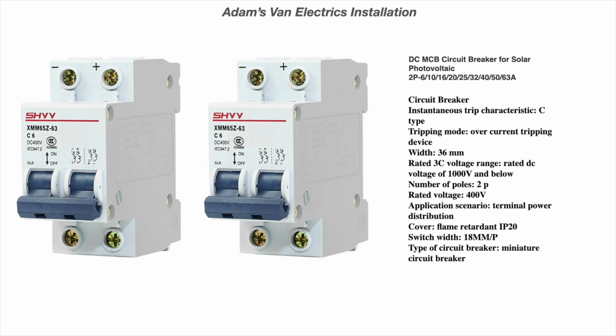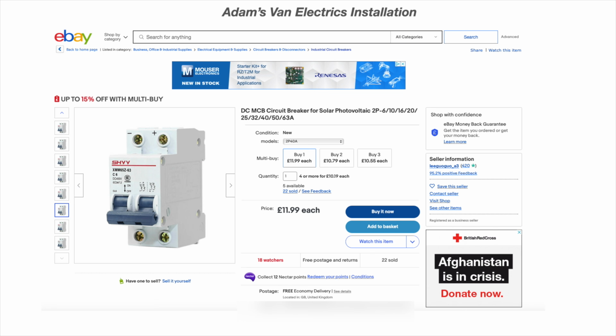We've added protection for those, which are DC MCB circuit breakers for solar. Make sure you get these particular ones - they're DC rated up to 400 volts. You can buy double poled trips, but they're not suitable for the DC side, so you must get the DC ones. They're very cheap - I found them on eBay, £11.99 each.